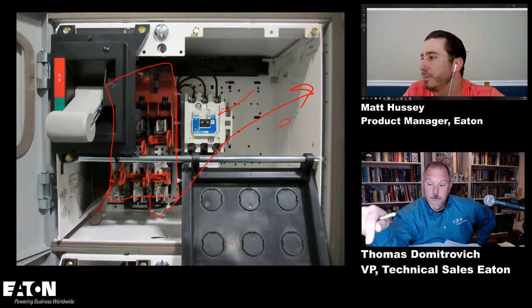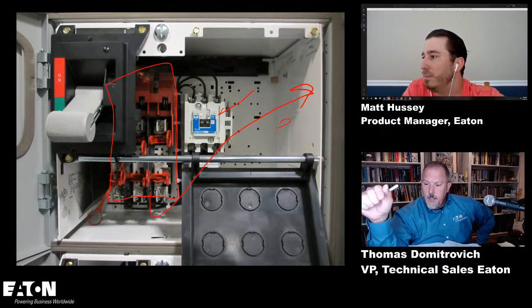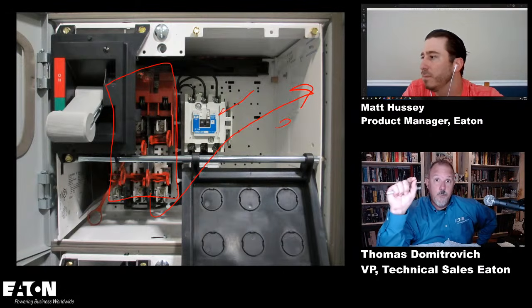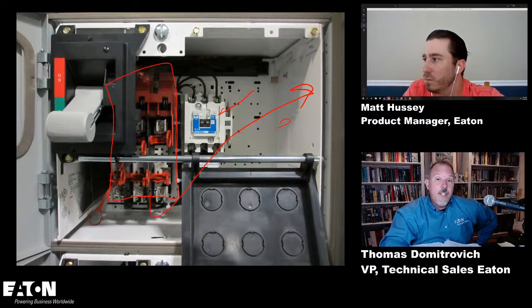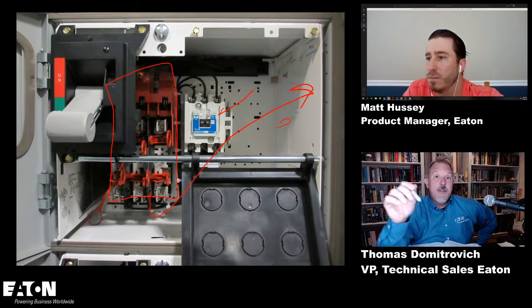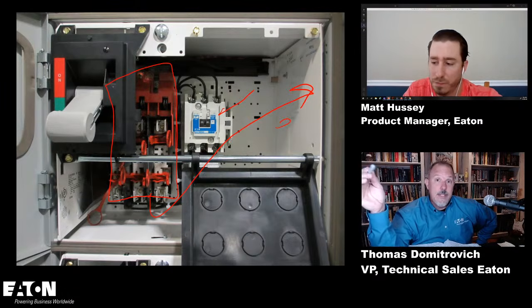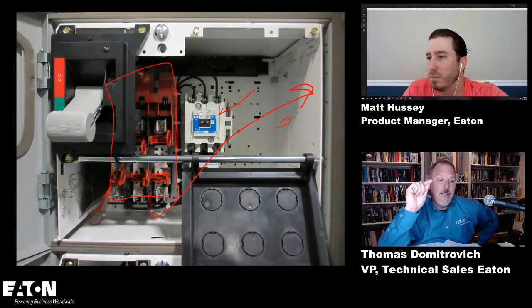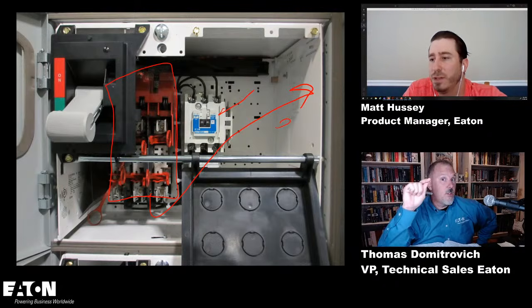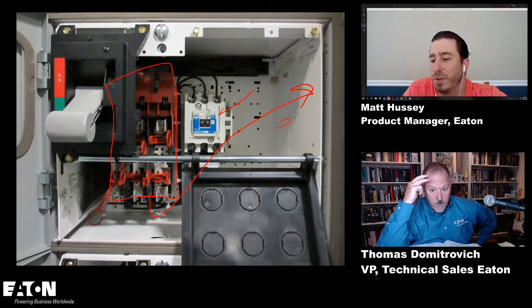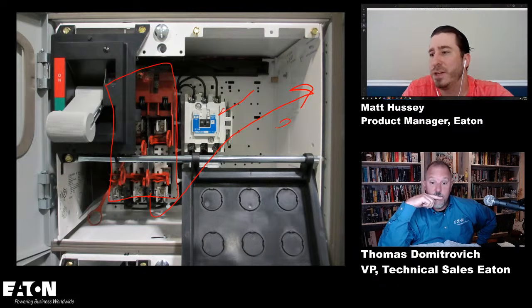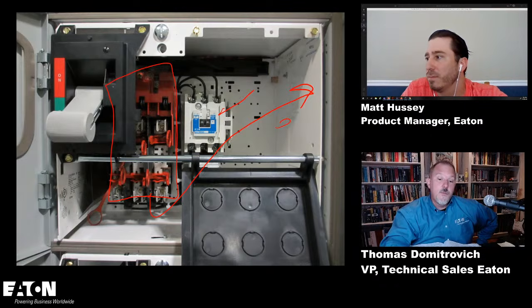Right. Mr. Gio Barone made a very good point: if you're looking at an MCC bucket and say there was an HMCP in there, an HMCP does not have an overload. It's instantaneous only. It's not a listed branch circuit overcurrent protective device. Yep. It provides short circuit protection only. That's right. It's a UL recognized component, so it has to be part of a combination. Now, this is a fusible disconnect, Matt. So I would assume I'm thinking of the fuse.